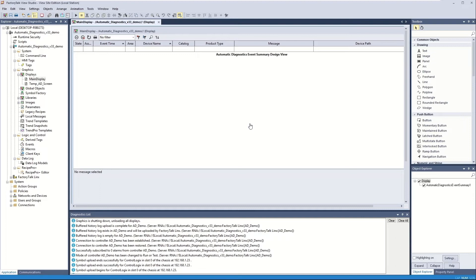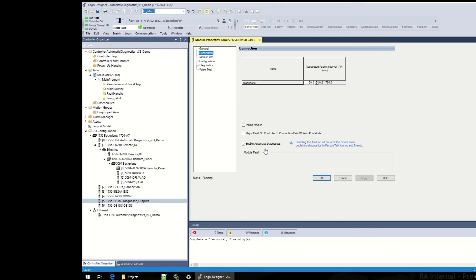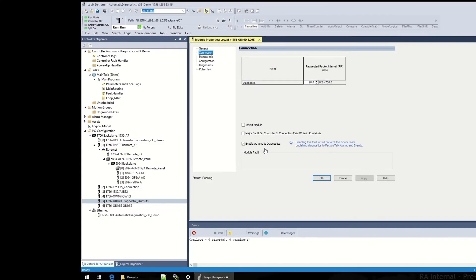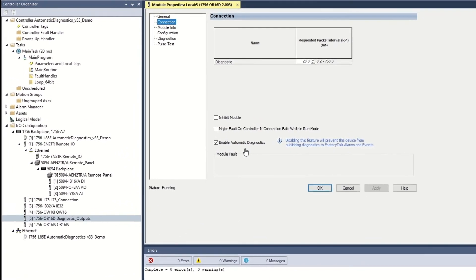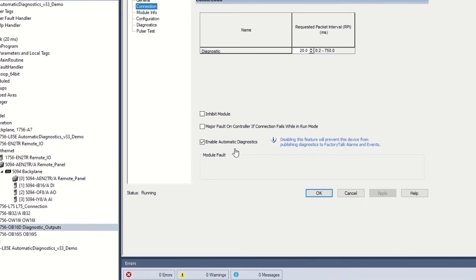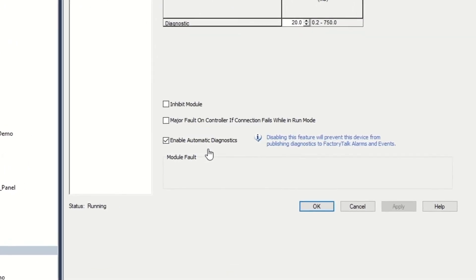With PlantPAX 5.0, adding the new alarm summary screen to the FactoryTalk SE HMI application at design time is made simple with the automatic diagnostics event summary frame from the new PlantPAX 5.0 framework library. After creating the new hardware alarm summary screen, every time you add new hardware, just click the enable automatic diagnostics box and alarms are automatically sent to FactoryTalk Alarms and Events.